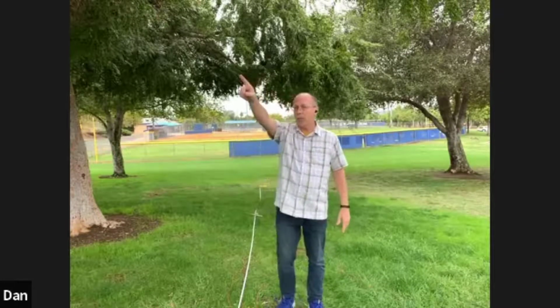So if you have high resistance, well, I'm actually going to back up. New installation: drive the ground rod early. Let it settle in, because you end up with air pockets around there, and that adds resistance. The other thing is drive it early and put it in an irrigated area. Start irrigating your soil, right? If you started from bare dirt that's bone dry, perhaps hasn't been irrigated for months, you're going to have very, very high resistance. If I had to put a ground rod over in that field, that's not the end of the world. I'm going to put one spray head or one rotor and just always irrigate that area to help keep the resistance down.